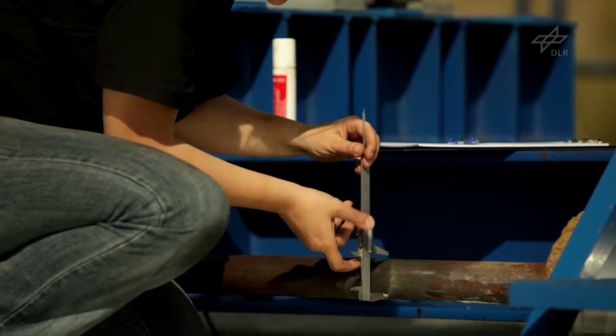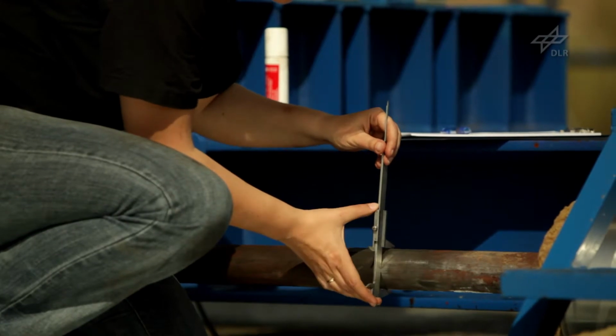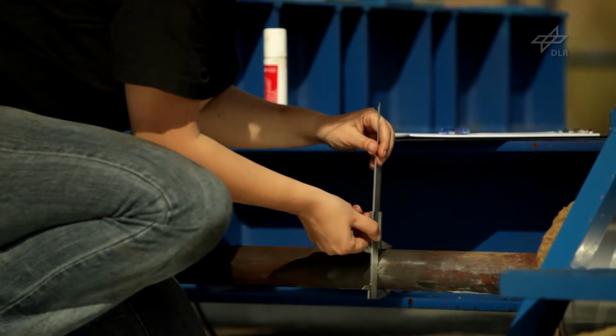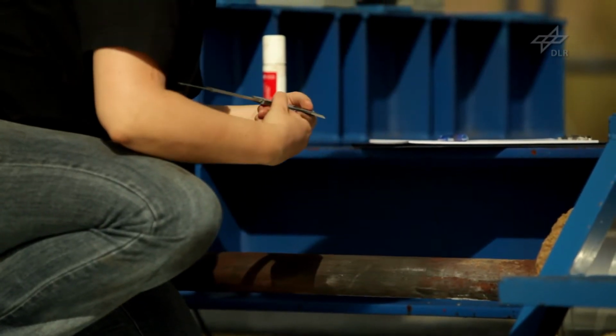In order to set up the flow sensors correctly, we need to know the geometry of the piping. So we will measure the outer diameter of the pipe and its wall thickness. For measuring the outer diameter, we use a sliding caliper. And we measure several times around the circumference of the pipe in order to get its average value.